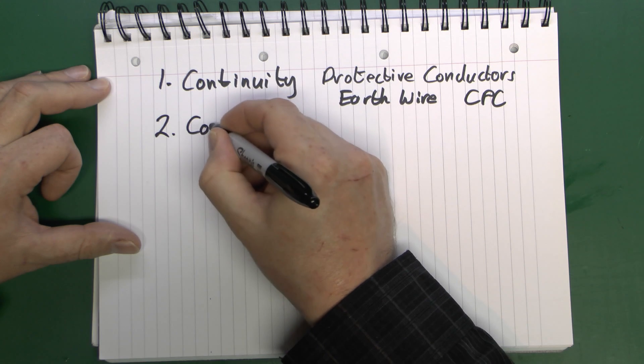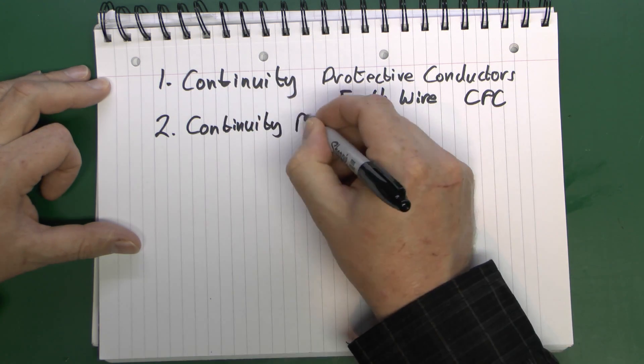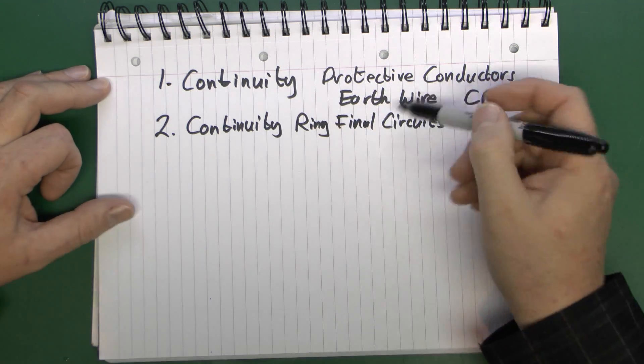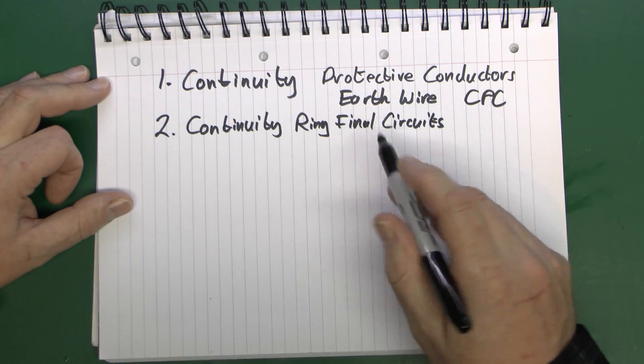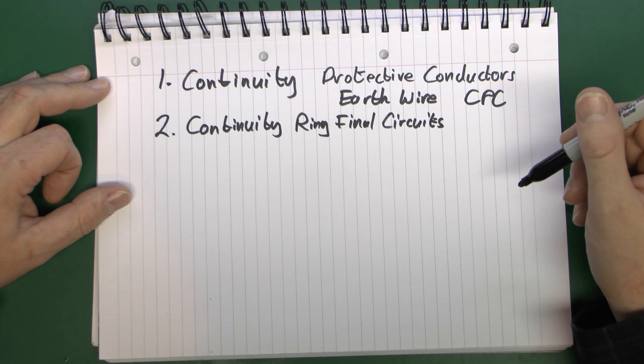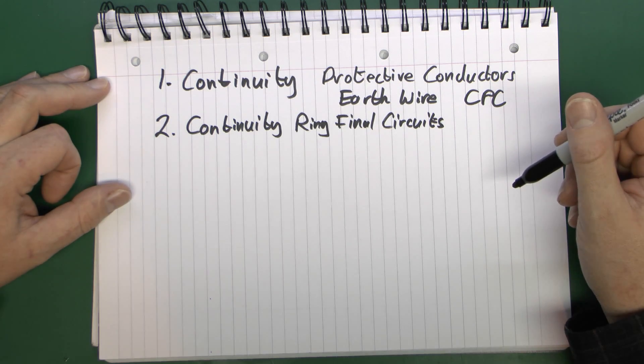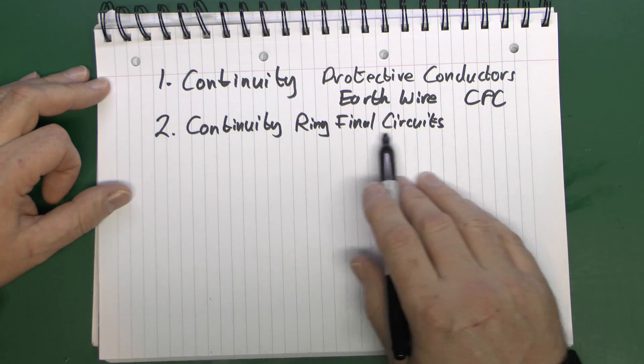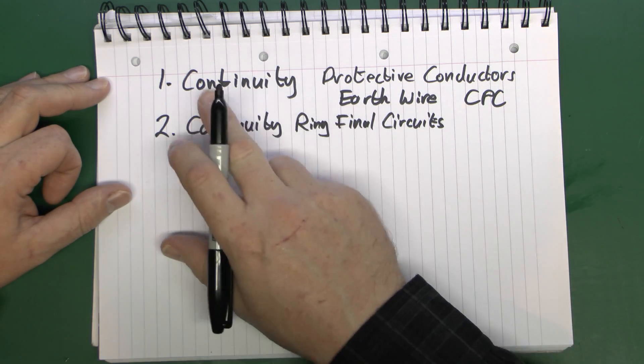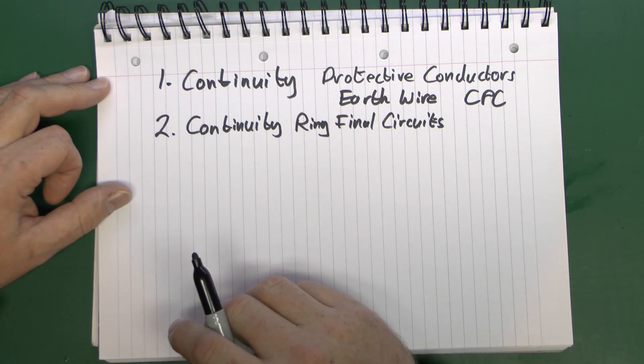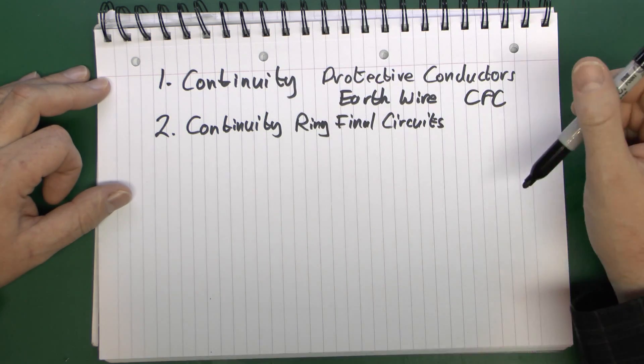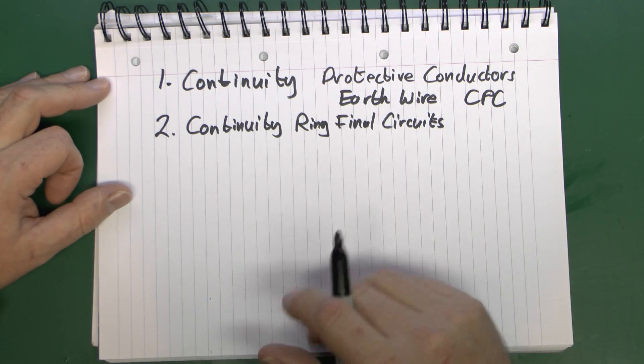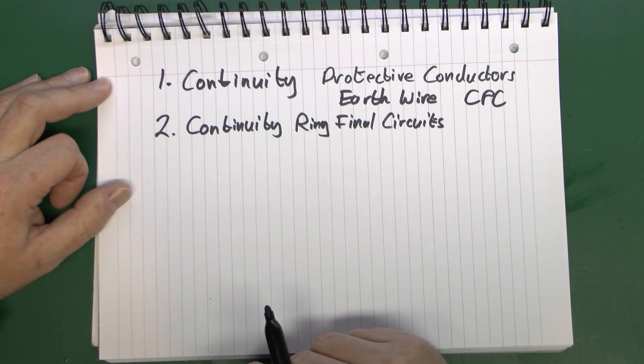Test number two is also continuity, but for ring final circuits. This actually covers the line, neutral and earth — both to make sure it's a ring and that they are connected in the correct place. One of these tests is definitely compulsory, so if you've got a ring circuit you're going to be using this one. For all other circuits you'll be doing test one. Of course, you only do the ring final test if you have a ring final circuit, and most circuits are not those.